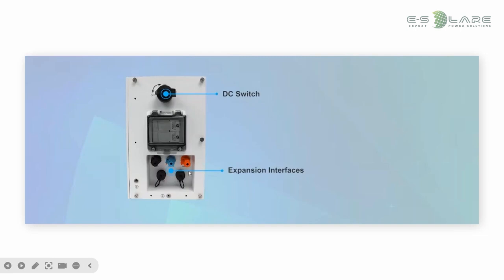So for our three-phase MID device, this inverter can connect a maximum of two stacks of batteries. Maximum is 60 kilowatt hours. And the expansion interface is for, for example, customers who have 5 or 6 pieces of battery. They want to stack them as 2 stacks. They can use this part. And here there are 2 fuses. If something goes wrong, you can just replace the fuse to solve the issue.